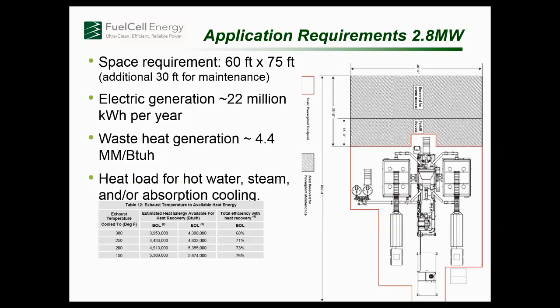So each one of those 2.8 megawatt fuel cells generates about 22 million kilowatt hours annually and about 4.4 million BTUs per hour of waste heat that can be used for, as I said, either hot water, steam, or absorption cooling.